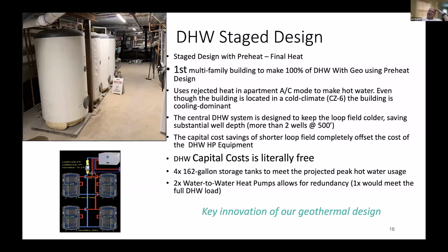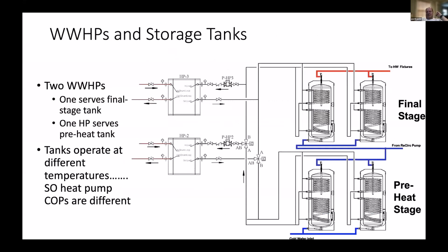So it's a little counterintuitive. We give you hot water for free if you put it in there, but the system can be made smaller and much more efficient if we're having this cooling effect by taking the thermal energy out of the loop in the middle of the summer or help cooling the loop for domestic hot water production. Again, this is just an idea about the stage design here. The COPs are going up due to the stage design, and we take advantage of exposing the heat pumps to as cold temperatures as we can to increase their efficiency.